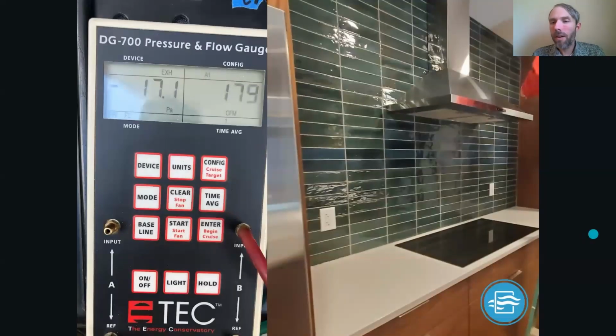Now, all LEED certified homes must have proper ventilation under the environmental quality ventilation section. And you'll work with your qualified energy rater to inspect the existing ventilation systems. This includes testing the kitchen hood ranges, bath fans, and supply fans if they're being used for the whole home ventilation system. The biggest issue will most likely be the kitchen range hood. At the very least, the kitchen range hood must be vented and ducted to the exterior and must pull at least 100 CFM while testing.